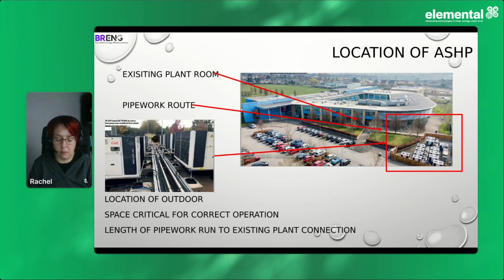Now, this is the challenge everybody's going to face with going to air-to-water heat pumps. This is a school we did, quite a large school in Leeds, and there's 12 air-to-water heat pumps down on the bottom right-hand side. Each one of those is 2 meters by 2 meters, and that's the amount of space we need to generate the same amount of energy that was already located in an internal plant room, which is arrowed on this screen down to the middle. So you've got to find a suitable location to put all the air-to-water heat pumps. Generally they won't go on the roof because they're too heavy, so you have to find somewhere around the perimeter of the school. But then you've also got to find a way of getting the pipework back into the school if you're going to reuse the existing heating infrastructure.